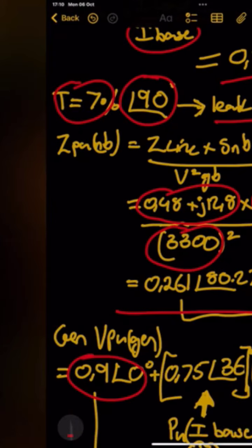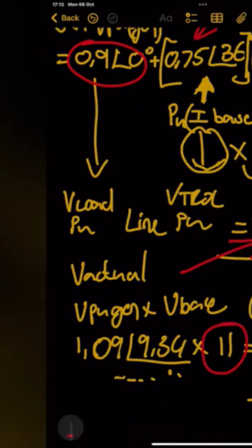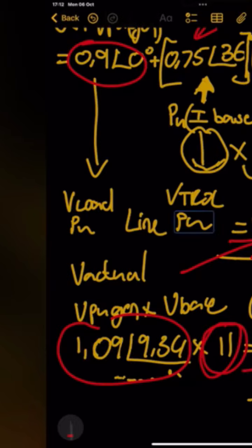It's simple. We basically use the current that is drawn by the load, and we know for a fact it'll also run through the transformer, which is at 7% impedance, as well as at 0.26, the line per unit impedance. You add them up and you basically get to this value over here. Now this value is the voltage at the terminals of the generator in per unit. So what you have to do, yet again, to transfer that to an actual value, is you multiply it with its V base. So the actual per unit value of the generator multiplied by its base, which is obviously 11 kV because its output is at 11 kV, which was its base, giving you a total of 11.968.